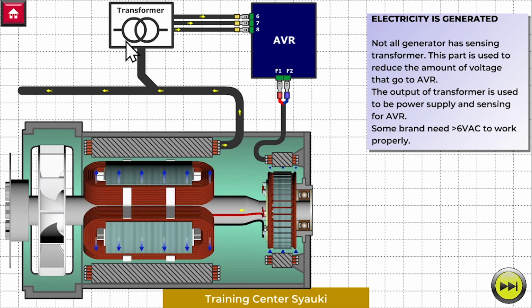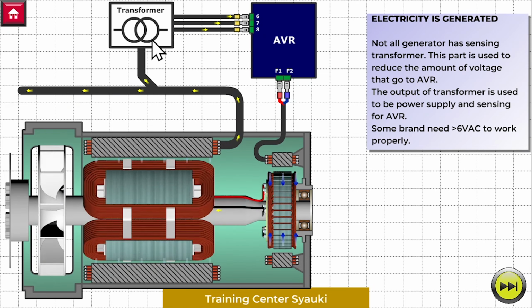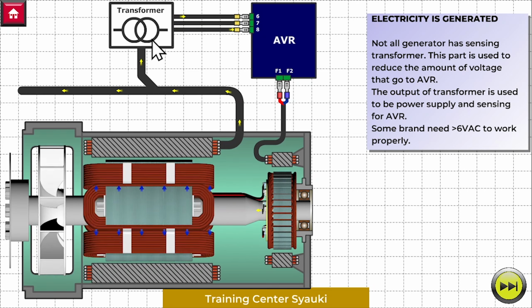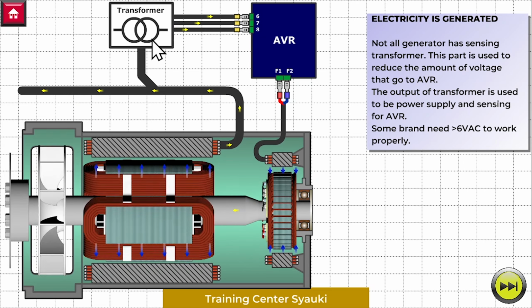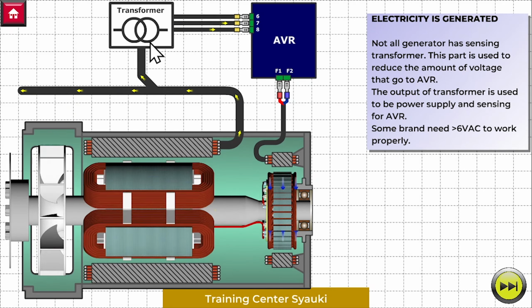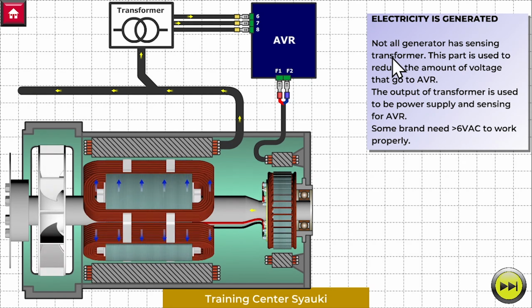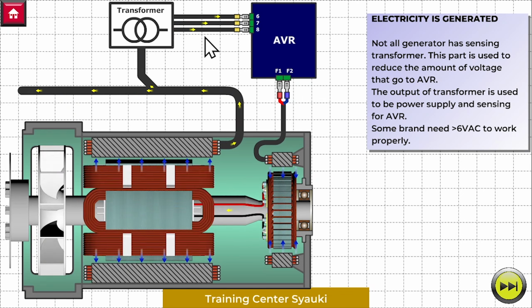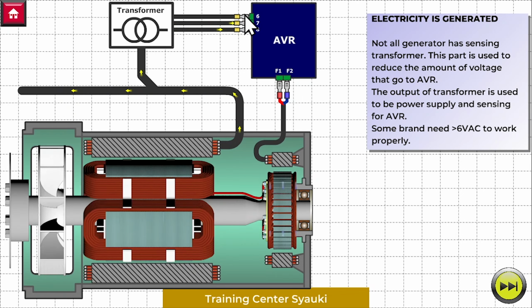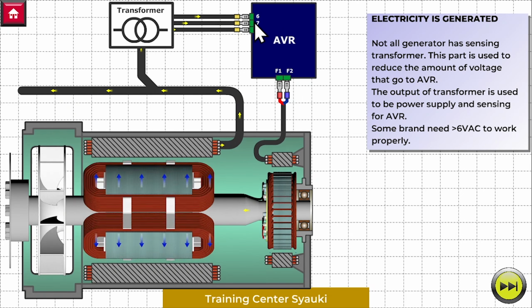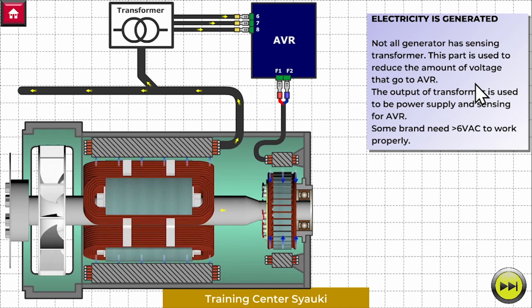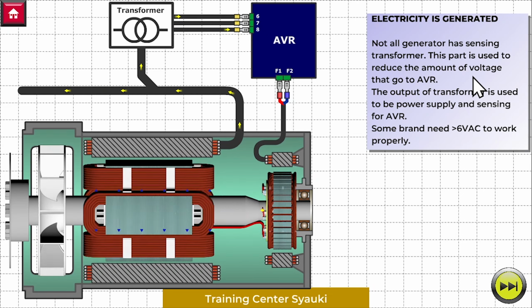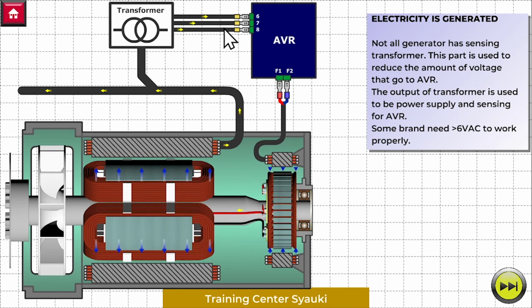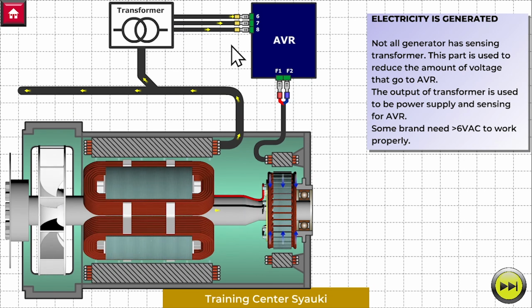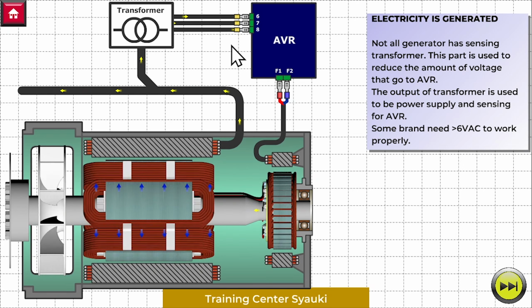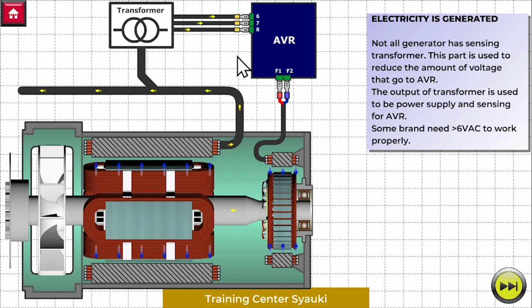Some people call this a potential transformer, or isolation transformer, but I prefer to say sensing transformer because it's used to give AVR sensing. This part is used to reduce the amount of voltage that goes to the AVR. The output of the transformer is used as power supply and sensing for the AVR.